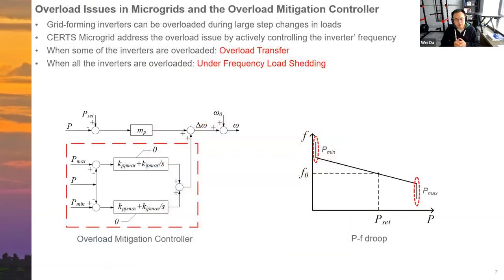As I mentioned, a grid forming inverter behaves as a voltage source behind impedance during normal operations. However, the grid forming inverter is not an infinite bus. It has its own power limitation and current limitation. So it is very likely that during microgrid operation, a large step change in the load can cause an overload of the grid forming inverter. So we need to deal with these overload events. For the CERTS microgrid, they designed a very simple overload mitigation controller, sometimes called the PMAX controller, that addresses this overload issue by controlling the inverter's frequency. Basically it is a very simple anti-windup PI controller added on the traditional droop control. When PMAX is reached during overload events, the droop curve becomes vertical.